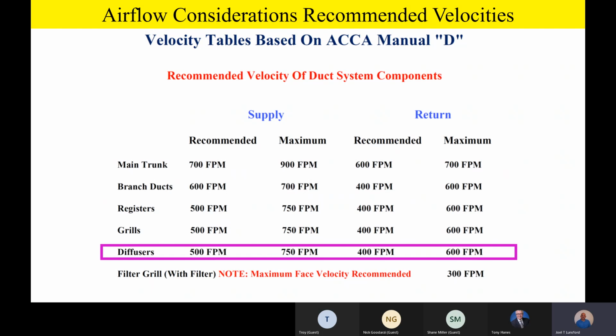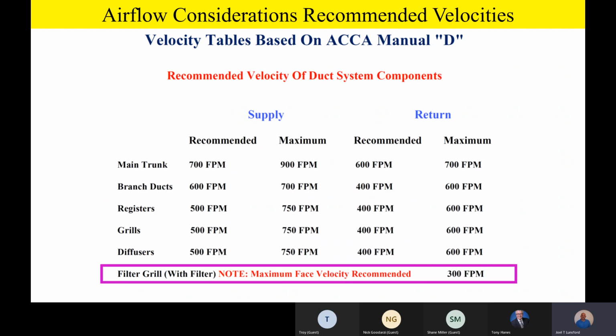The big thing to remember is if you do have a filter grill, do not exceed 300 feet a minute velocity across that filter grill. That's right out of Manual D. So when you're building your duct system and setting them up, be sure and nail that velocity where it needs to be on your duct components, as well as provide that 400 CFM per ton that is recommended.